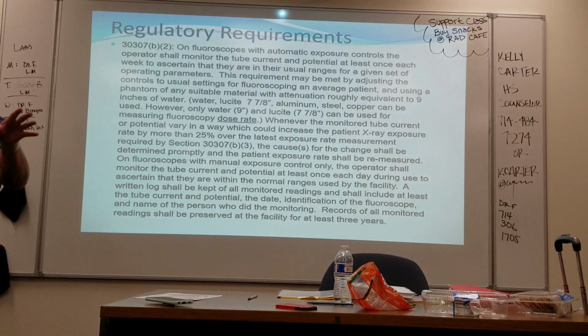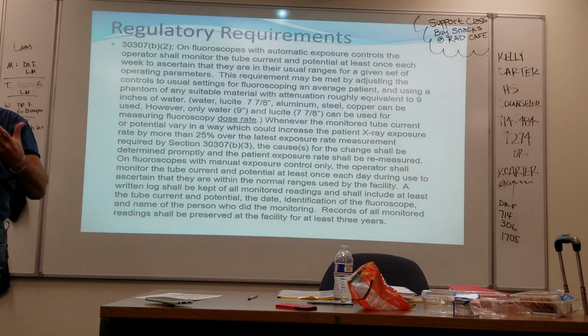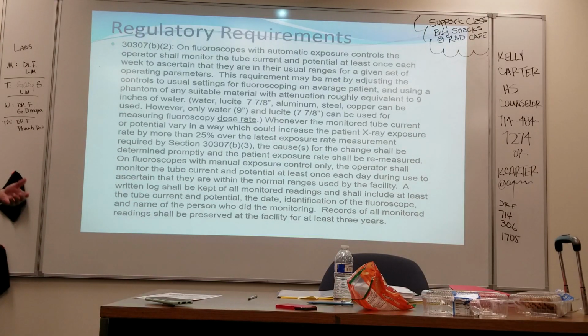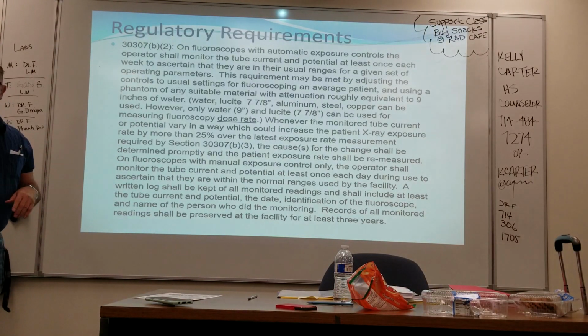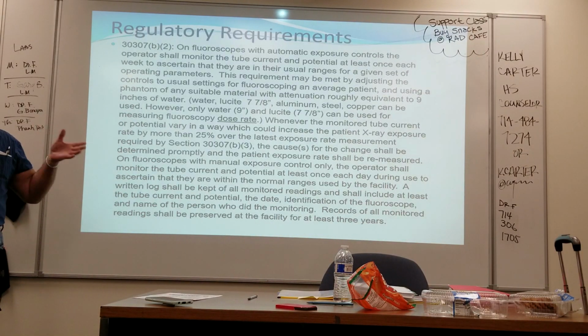Wherever facility that you work at, there will be weekly fluoro checks. What they use and how they do it, you're going to have to check with the facility that you ultimately work at. But that is a state requirement. Okay. Records have to be kept for 3 years. Guarantee you when an inspector walks in, they're going to ask for those. And they're going to expect to see them every week.